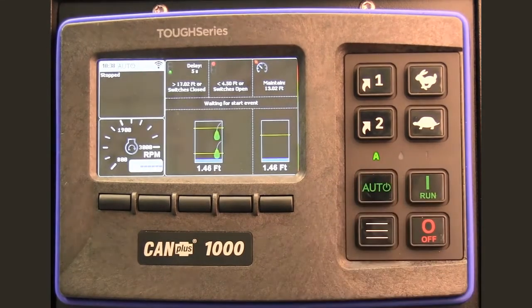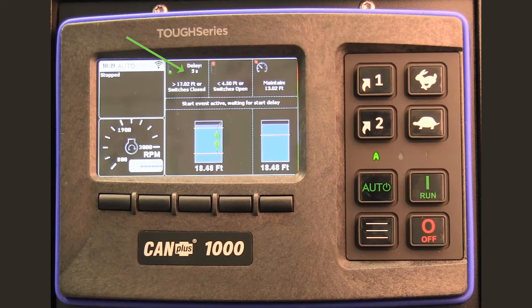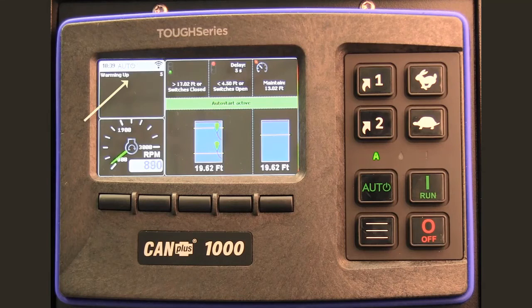Activate the auto start mode. The tank fills, causing the bottom float to go active, and continues until the start level is reached, causing the start delay to count down. The engine cranks, warms up, ramps to the intermediate speed, pauses at the intermediate speed, ramps to the run speed in maintain mode.